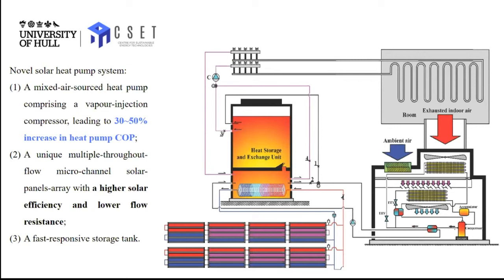So whenever in the afternoon or evening, solar radiation is less and not available, we got heat stored in the storage, being released and delivered to room space for heating. In this way, we would be able to extend the service time of the solar system and reduce the operational time of a heat pump. That means we can significantly reduce electric consumption of the heat pump. We can maximize use of solar energy, minimize use of the heat pump, which can save electric energy. These are the three major parts of our system.